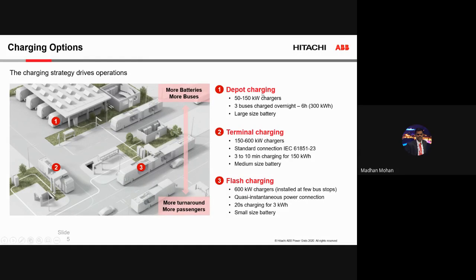The first one is depot charger, number one in the picture. When the buses are in the depot, you can put the buses on charging. It could be a slow charger, that's what we call depot charger. The converter rating is around 50 to 150 kilowatt. If you only go for depot charging, you will need a large size battery, and you need to put the buses on the charger for around 6 hours at the rate of 300 kilowatt hour.